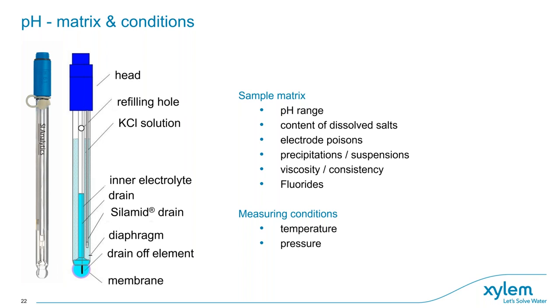When you want a good measurement, consider: the pH range you want to measure, the content of dissolved solids, extremely high or low ion concentrations, electrode poisons, precipitations or suspensions, the viscosity of the sample, and measuring conditions like temperature and pressure. Inside the electrode are many functioning parts — it looks just like a stick but has a lot going on inside to produce a good measurement.